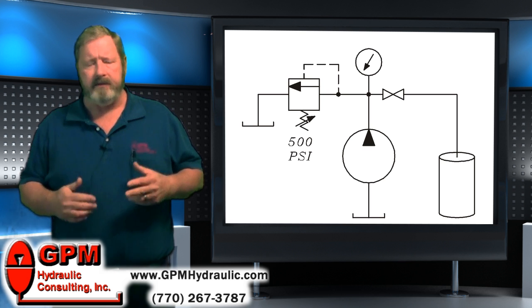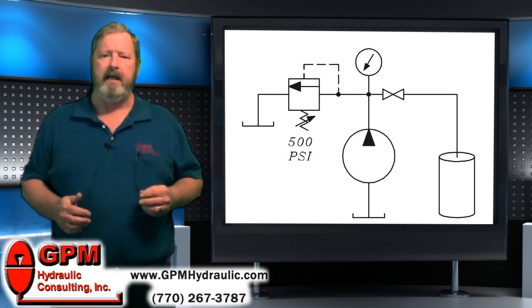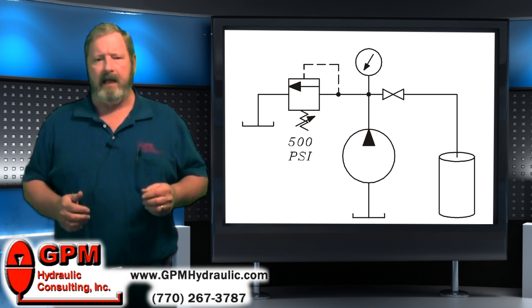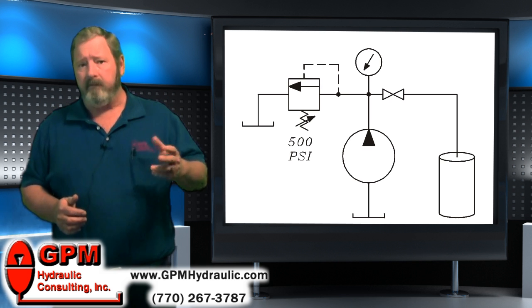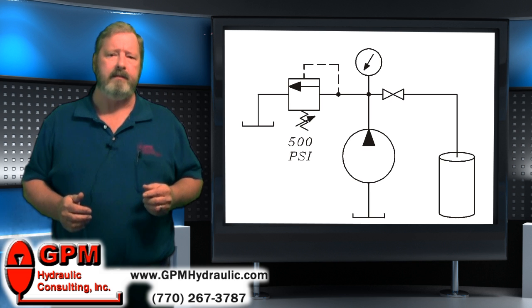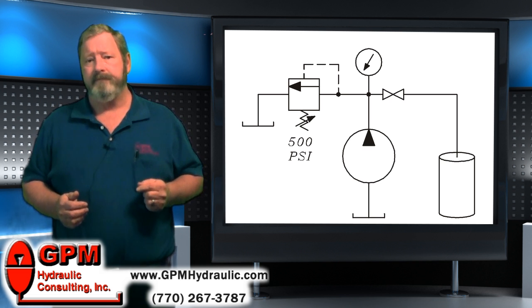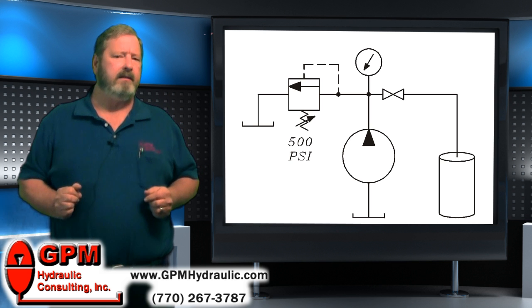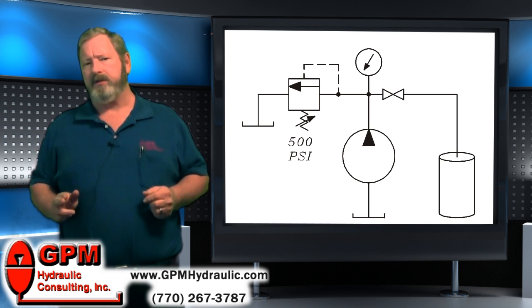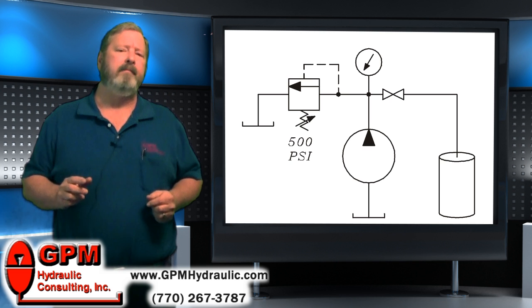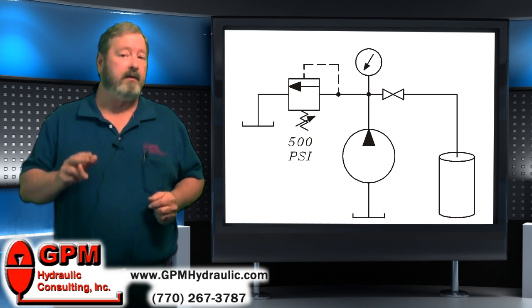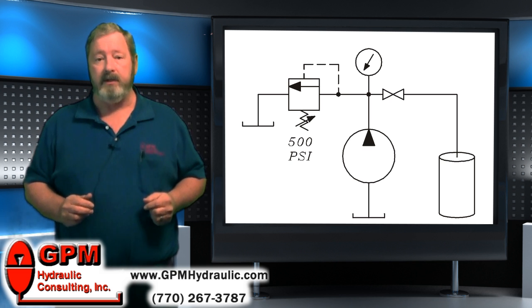The pump doesn't pump pressure, it delivers a rate of flow. That flow meets with, and hopefully overcomes, a resistance, and the result of this is pressure. So what you're reading on a gauge is not how much pressure the pump is putting out. What you're reading is the amount of resistance currently being overcome in the machine.